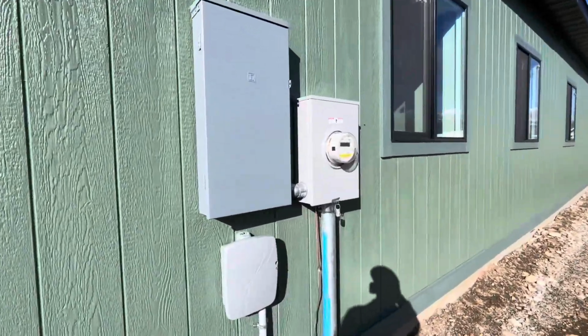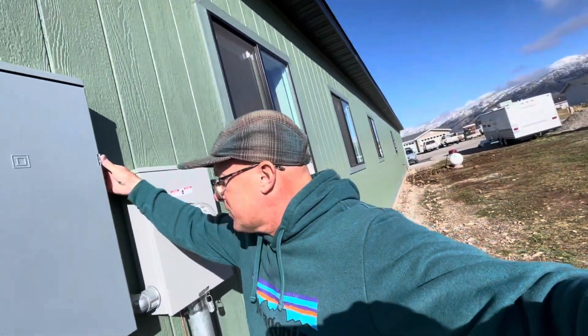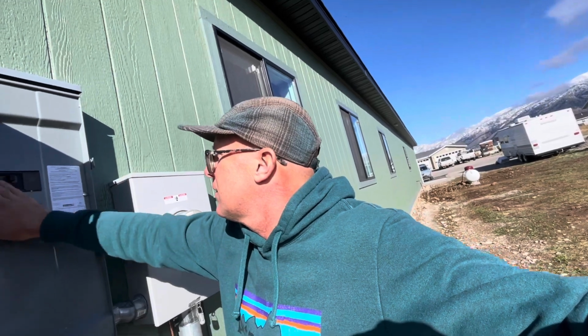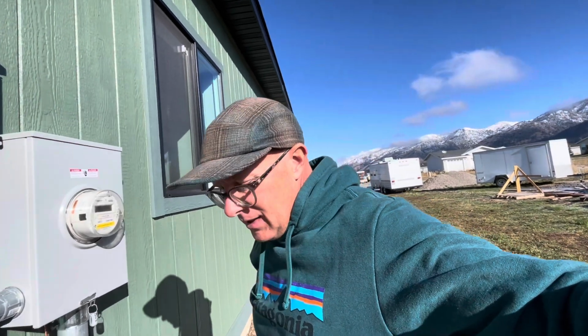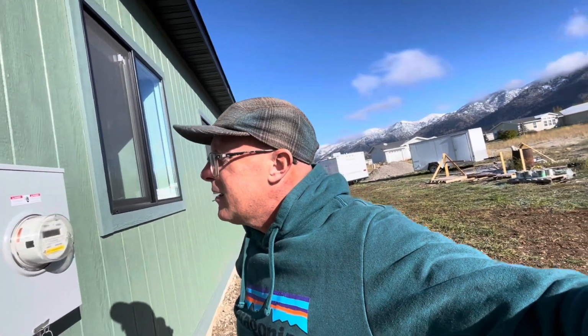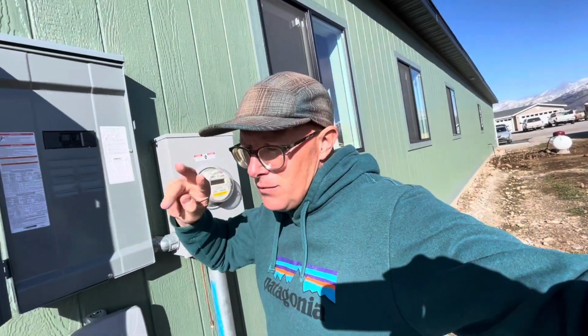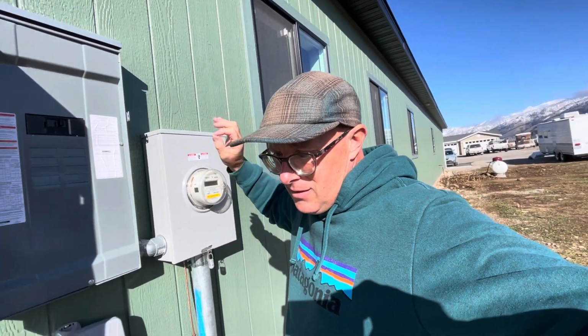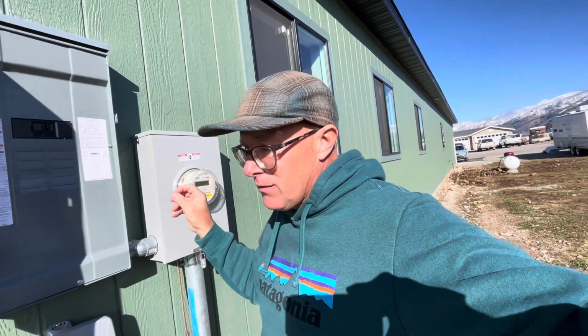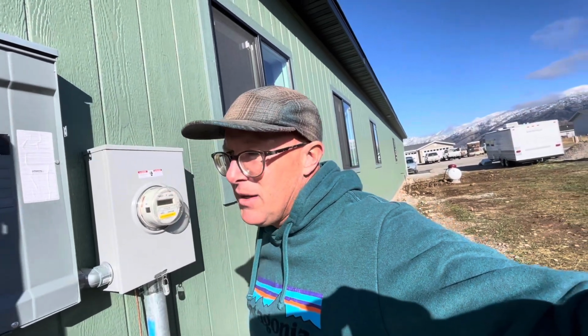So we're having problems starting yesterday afternoon. This disconnect panel just started popping, and it just clicks off constantly. We had an electrician come over last night and we walked through the house, and I can keep everything in the house on except for cove heaters. And if I click on one of the 3 cove heater circuits, this pops, but it doesn't trip the individual breaker for the cove heater, and it doesn't trip the main power breaker on the inside panel.